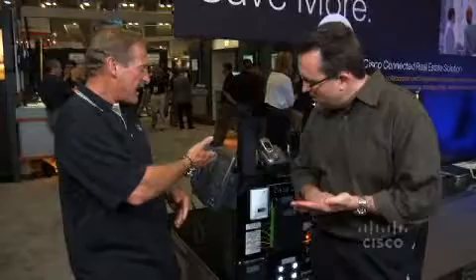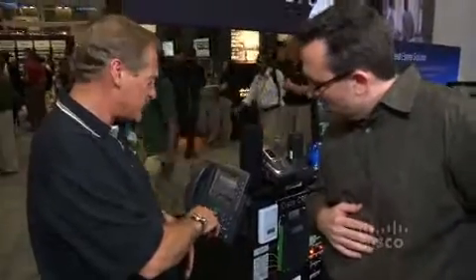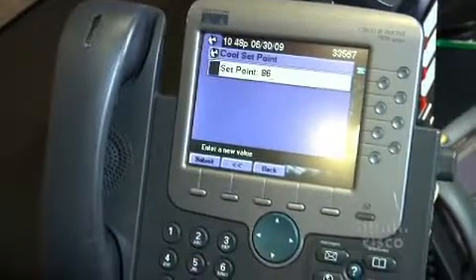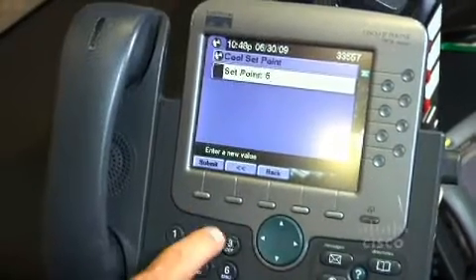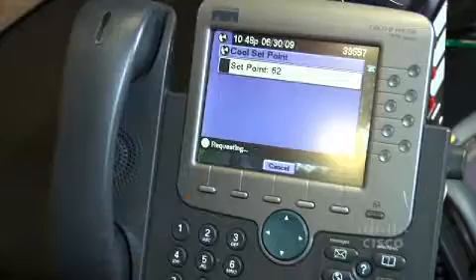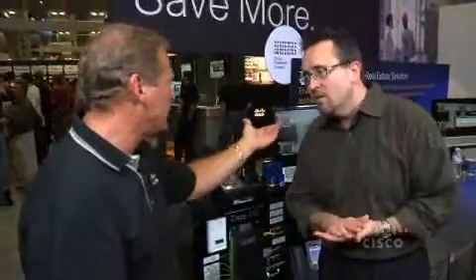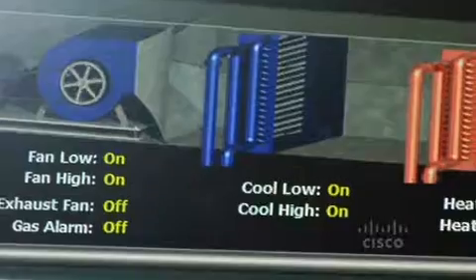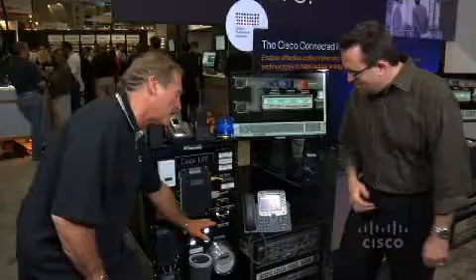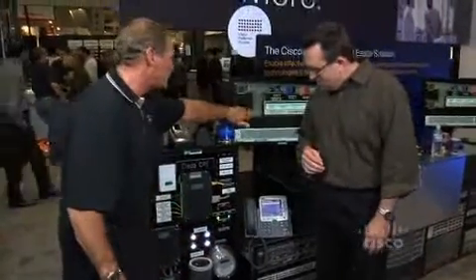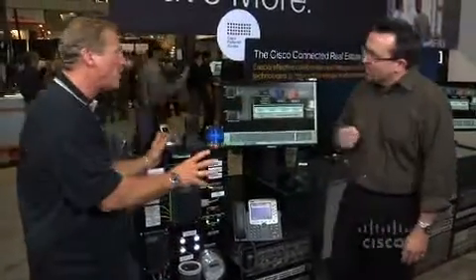As you notice on this phone over here, I actually have controls where I can control my lighting system. But also my HVAC system. So if I go down to my cooling set point, select that, and put a new setting in here itself, and submit that. Now I like that a lot, because once you put it on IP, almost the world is your oyster, right? It changes the whole user interface and experience. So if you notice on the screen, it changed over to cooling. Not only did it change over to cooling — I can feel it. The AC's kicked on, you can feel the fan, the dampers. It actually gives you true damper positions in your system, so you know what's going on in your HVAC system.